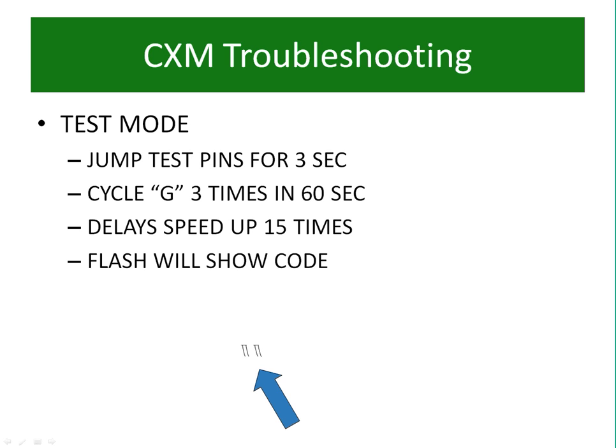Or the same exact way to also access that information is to cycle the fan switch on the thermostat 3 times within 60 seconds. That is the same thing as jumping those test pins. If you wanted a homeowner to go ahead and count the blinks, or more importantly, let him listen to the alarm relay clicks without taking the door off the cabinet, you can have them cycle that fan switch 3 times within 60 seconds. Have them listen for the clicks and tell you what that is. That might allow you to show up a little more prepared if you're comfortable with that.